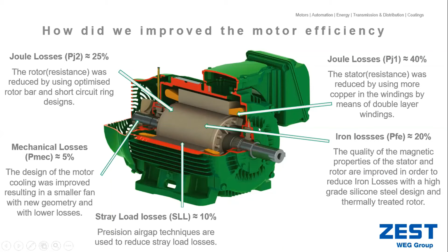If we look at where the biggest gains are, the Joule losses in the stator, the Joule losses in the rotor, and the iron losses in the rotor together account for 85% of losses. So there's not much more we can do on a motor, except that all the changes to make it more efficient happen on the inside.